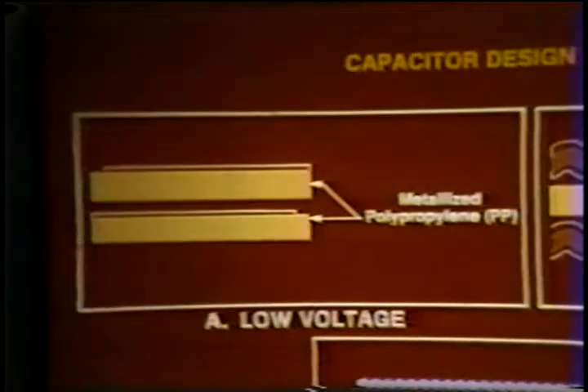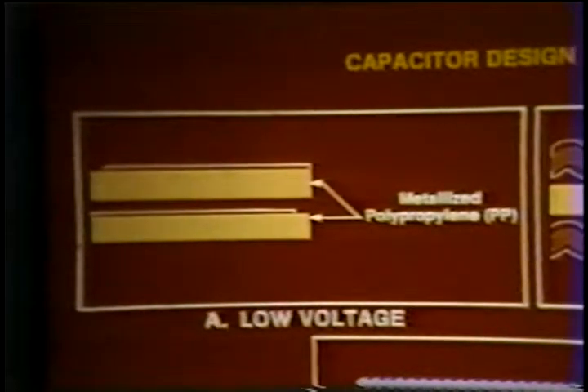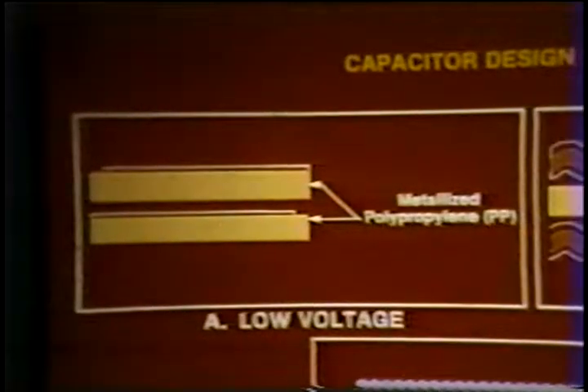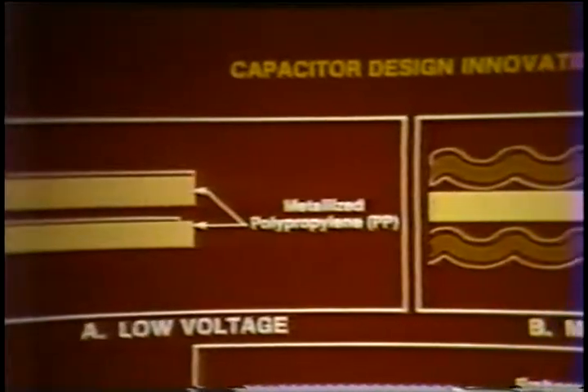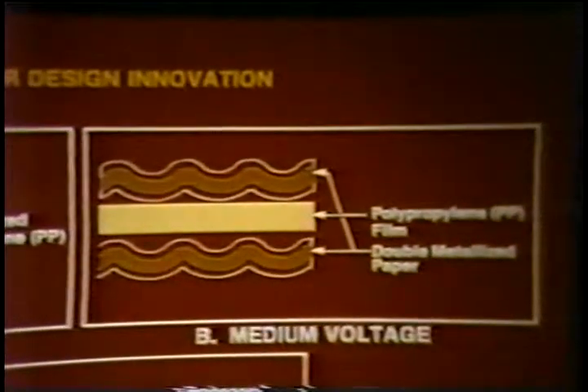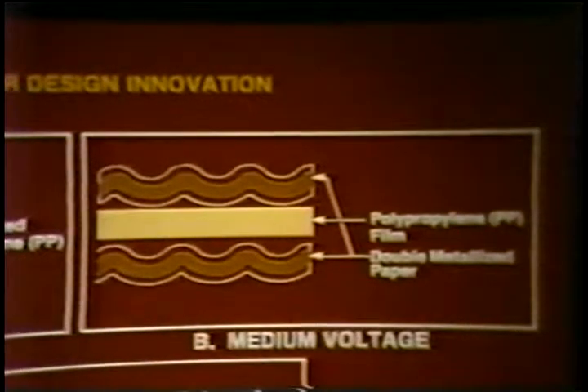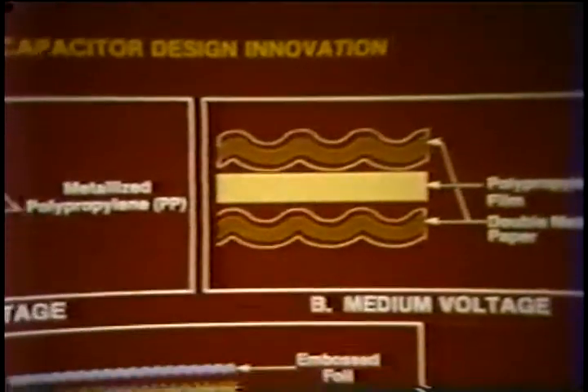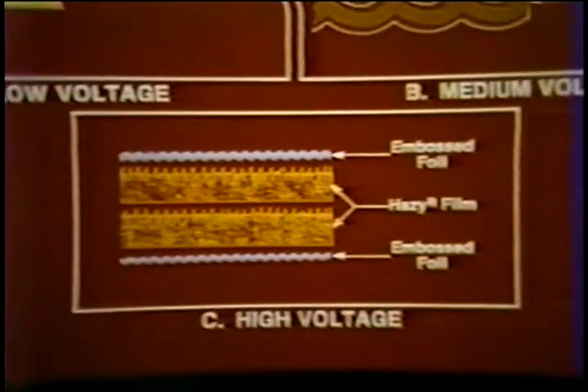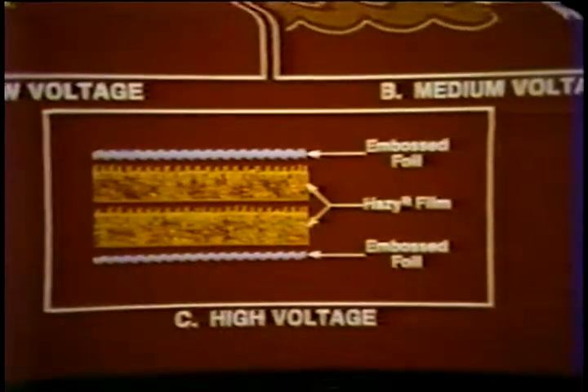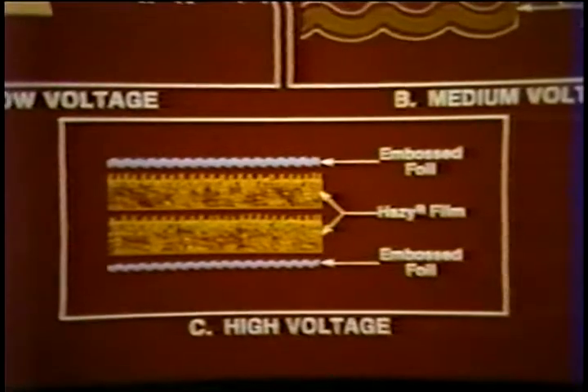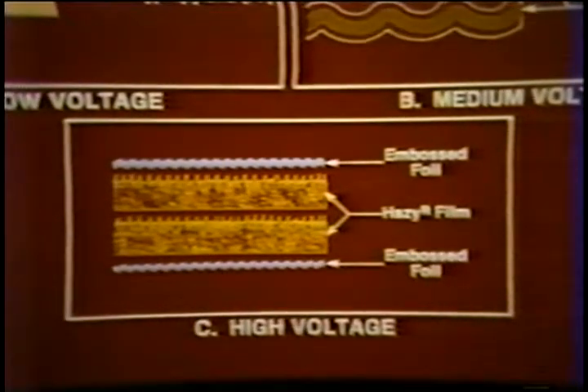Now that we're all experts on the fundamentals of capacitors, I would like to discuss some of the main constructions that are used for high, medium, and low voltage capacitors. In the low voltage area, approximately below 500 volts, metallized polypropylene is used. Aluminum is vapor deposited on the polypropylene film. As we move to a higher voltage, the electrode changes to metallized paper. Again, polypropylene film is the dielectric of choice. As voltage is increased still further, we again see the use of polypropylene film. However, here the film has a textured surface called hazy film and embossed foil.